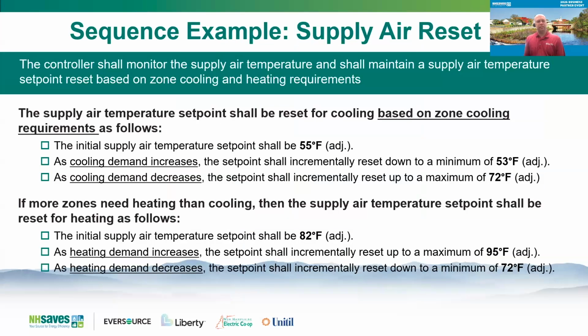Just wanted to show a sequence example to give you a flavor for what they look like. So here is a supply air temperature reset. The controller is going to modulate the supply air temperature based on zone cooling and heating requirements. The supply air is going to start at 55, and as the cooling demand increases, it's going to reset that air a little cooler. As the cooling demand decreases, it's going to raise that temperature up to 72, which would basically minimize, if not eliminate, reheat. And then the same on the heating side.